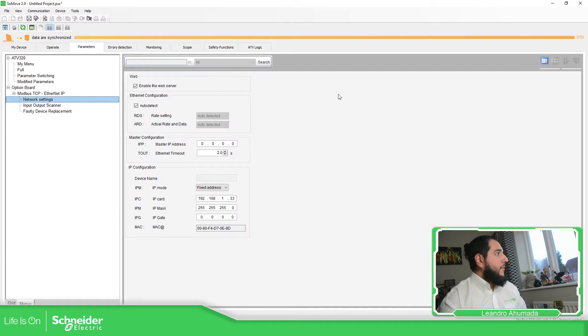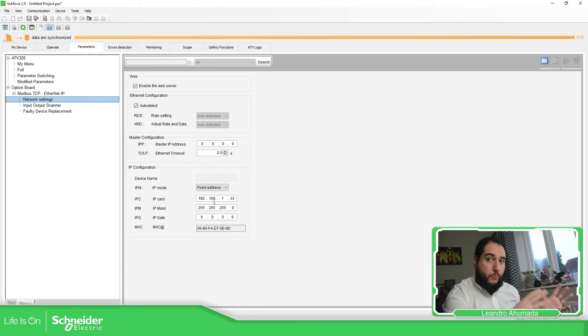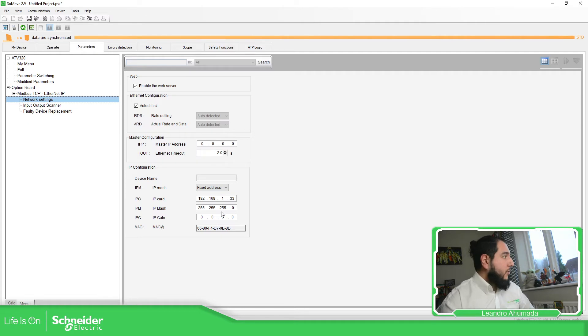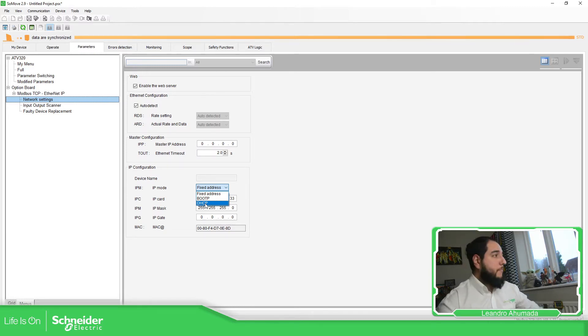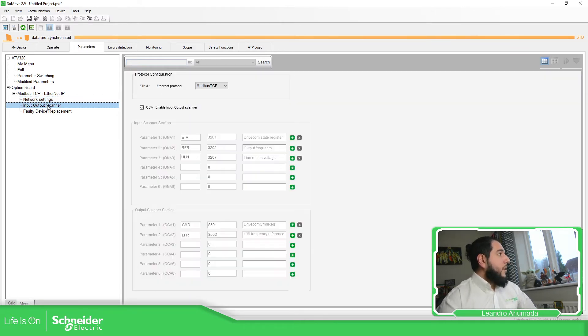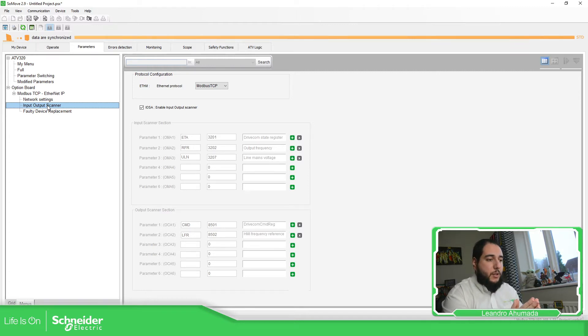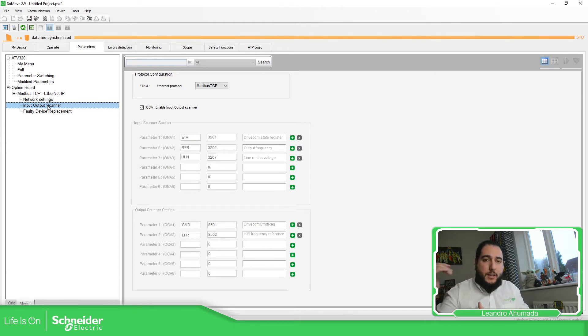Here you have the network settings, so you can see the same IP address that you have already configured. This is something important: if you're going to use DHCP, that's going to affect the configuration that we have for the PLC. In my case, I use a fixed IP address. The other important thing is the input/output scanner, which are the registers that the client can read.